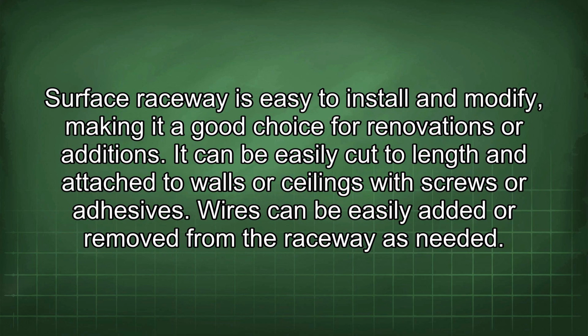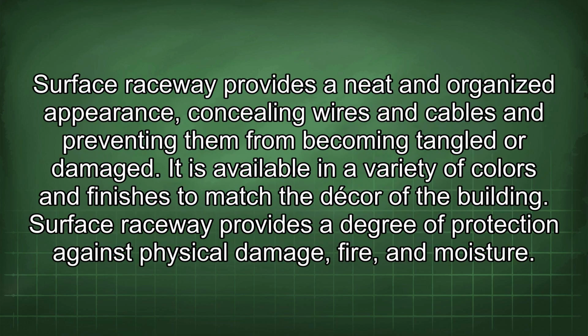Surface raceway is easy to install and modify, making it a good choice for renovations or additions. It can be easily cut to length and attached to walls or ceilings with screws or adhesives. Wires can be easily added or removed from the raceway as needed. Surface raceway provides a neat and organized appearance, concealing wires and cables and preventing them from becoming tangled or damaged. It is available in a variety of colors and finishes to match the decor of the building. Surface raceway provides a degree of protection against physical damage, fire, and moisture.